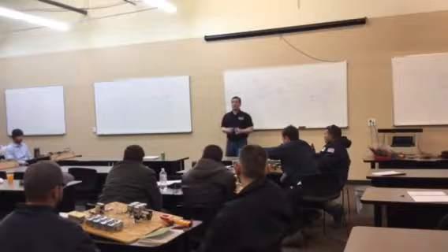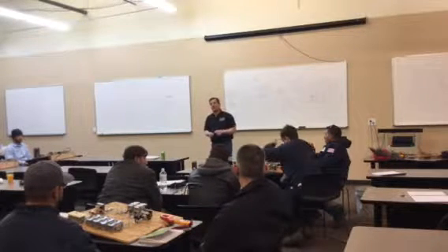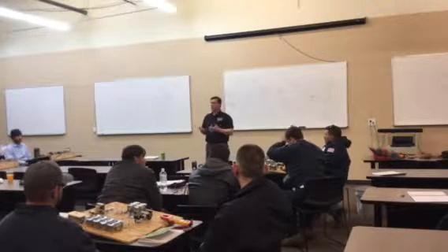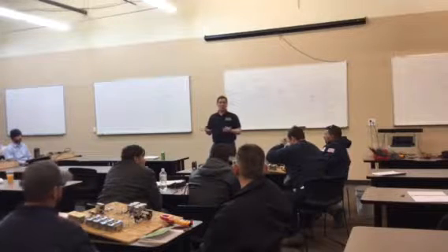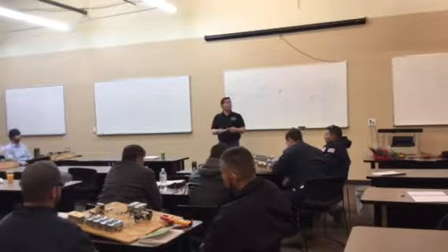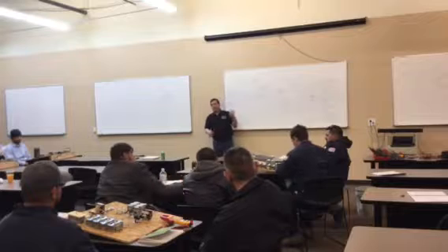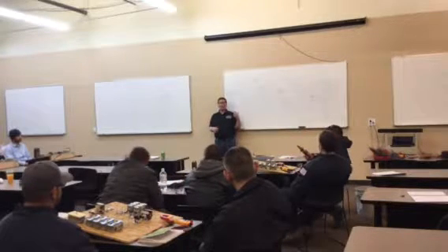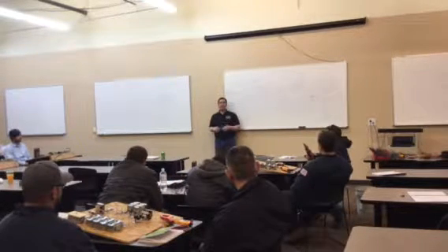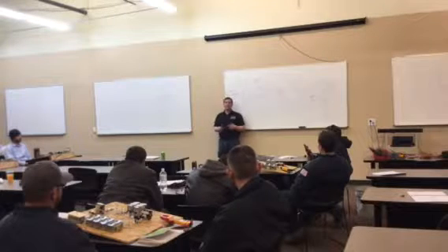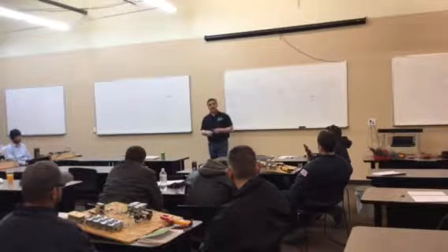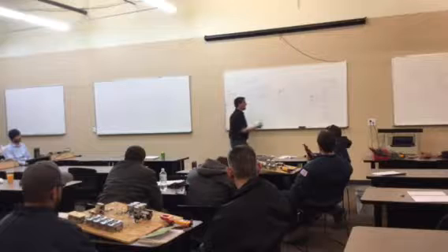The transformer is a really good example of a limited supply of power. It's sending out voltage, but its ability to power devices is limited to its inherent design. We call that VA — we'll get more into VA later. The voltage being present here is not necessarily a representation of power; the VA is a representation of power. VA is a mathematical equation.